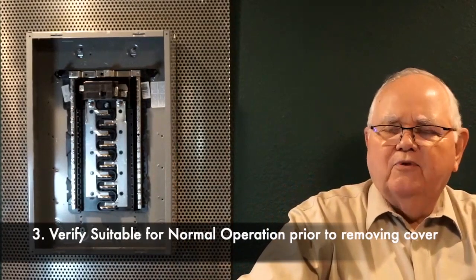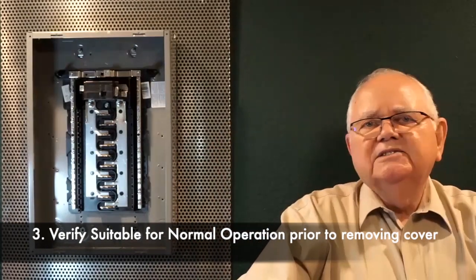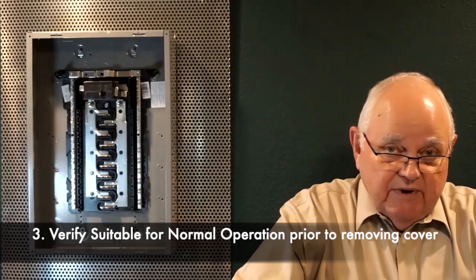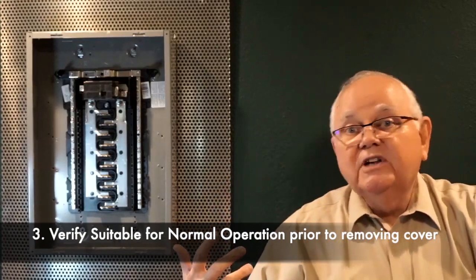The next thing that we're going to do is we're going to make sure that our equipment is suitable for normal operation. So before we ever pull this cover off, NFPA 70E gives you 6 items to look at to make sure that this equipment is safe to operate the breakers on the outside or pull the cover off and go in and verify an electrically safe work condition. So what are those things we're looking at before we ever pull the cover off? Well, first thing, we want to make sure it's properly installed, it's been properly maintained, that it meets all its requirements for whatever its use is for the manufacturer's instructions and UL and so forth. We want to make sure that all the covers are in place, that all the bolts would be in place before we'd operate anything on this equipment. And we'd make sure that there's no signs of impending failure. If we meet all of those requirements, then we're safe to pull that cover off if we wear the appropriate PPE and follow all the safe work practices in.